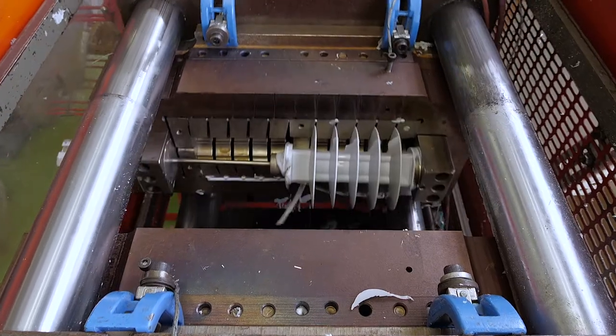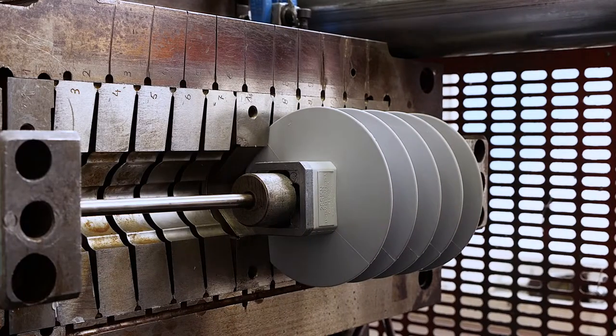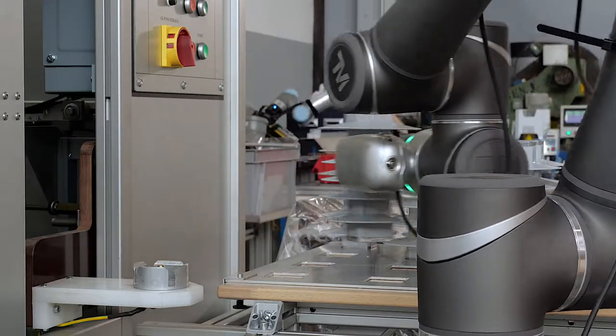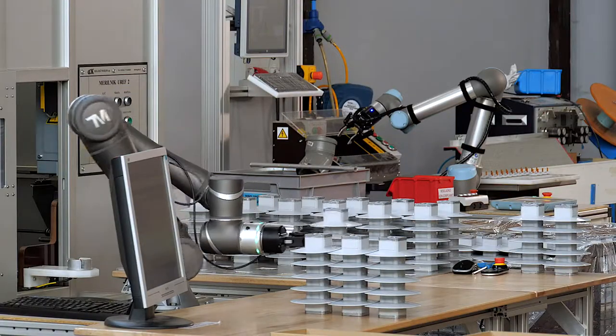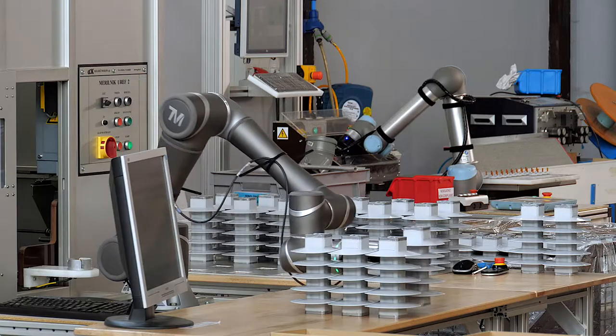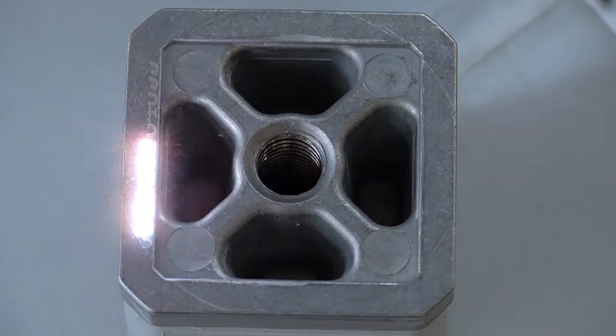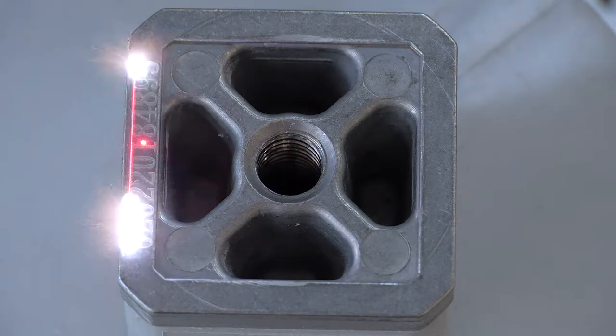After siliconizing, all surge arrestors are 100% tested on calibrated devices where partial discharges, reference, and residual voltage values are measured using routine tests. The reference number of the conducted tests is then engraved onto each surge arrestor.